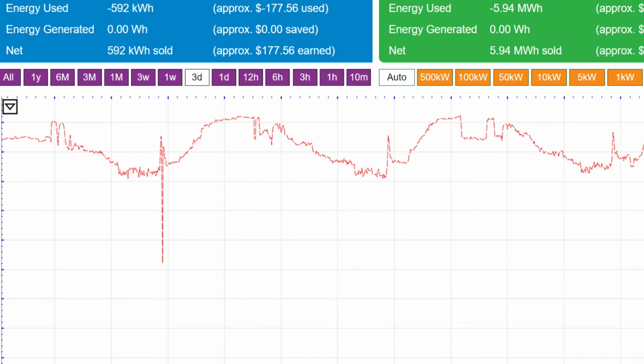Those spikes are the Carrier unit's logic reacting to the super slow flow rate of the refrigerant. It gets so slow and uses so little power that the unit actually turns itself on for a moment to collect humidity from the space, to keep the refrigerant from getting too sluggish, from slugging up. That's how incredible this Carrier unit is, and how smart the algorithms in it are, to be able to maximize the use of the SunTrack panel.